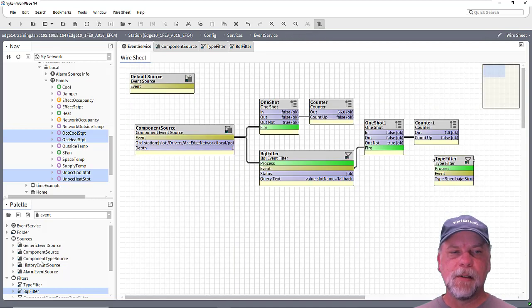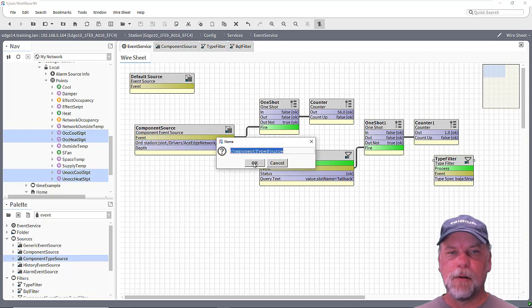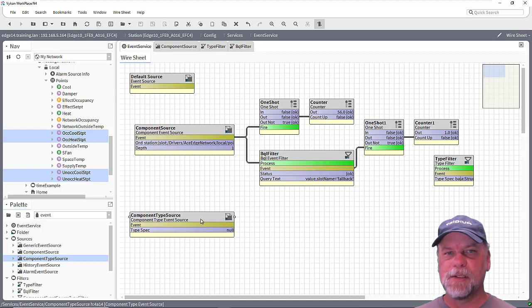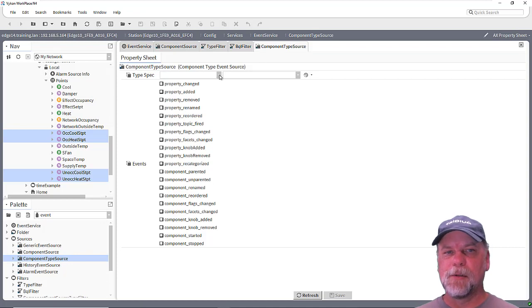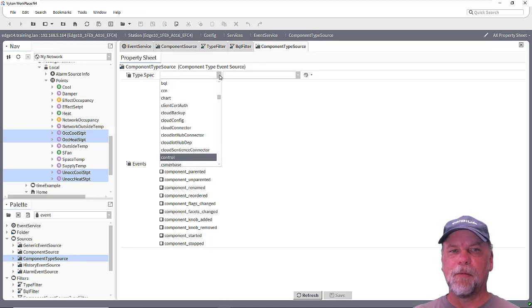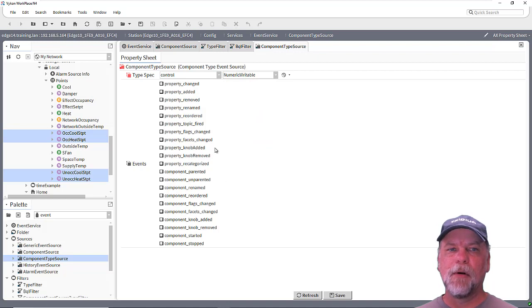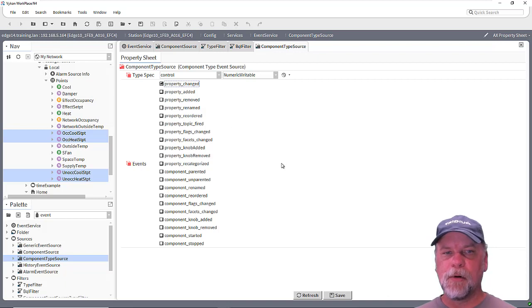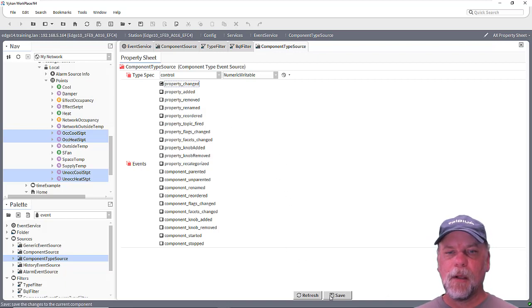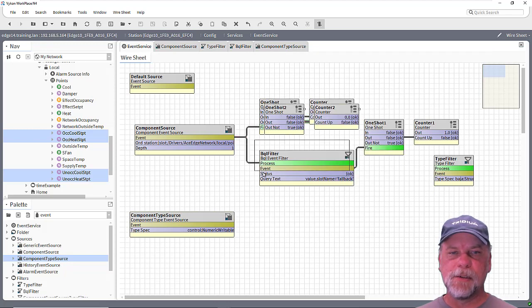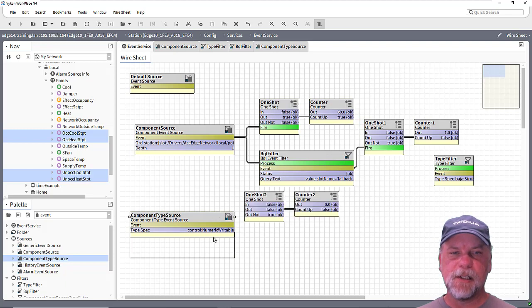Now another option is the component type source. What this allows me to do is to subscribe to everything of a certain type in the station. So with the component type source, you have the type spec selector, and I can pick from the control module and then maybe a numeric writable. And then we still have the same component events that we can filter on — property changed, property added or removed, or knob added or removed. So in this case we'll check for any property changed from numeric writables. And we'll go ahead and duplicate these counter and one shot components as well, just so we can see the event firing.